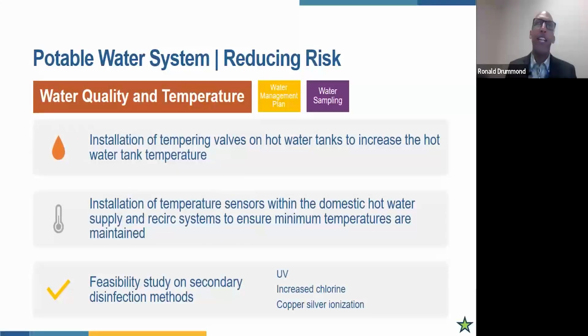So on this slide, I just wanted to talk about some other ideas or items that can help with maintaining hot water temperature in your network. They include temperature sensors on hot water tanks and throughout the domestic hot water system. If sensors in the field demonstrate lower temperatures than required, it's probably a good indication that you've got an issue there. So it's a good way for facilities to be proactive in trying to determine maybe there's a cross connect there, maybe there's a dead leg, maybe there's a check valve that has failed, maybe there's a leaking pipe somewhere, but it's an indication that there's probably some maintenance that has to be done.